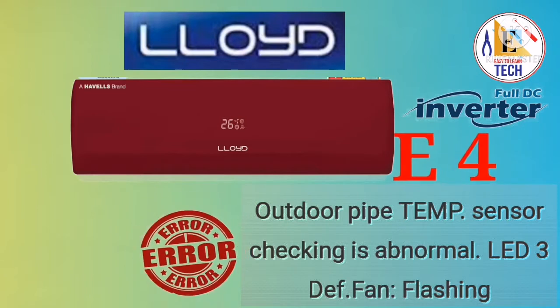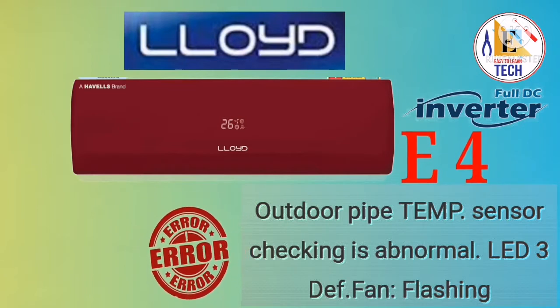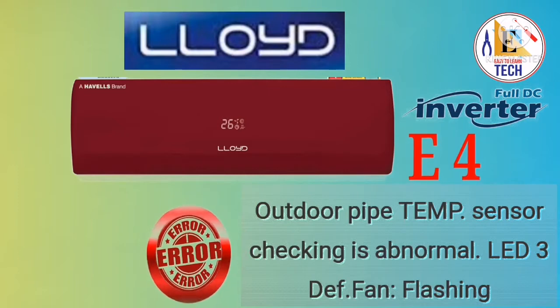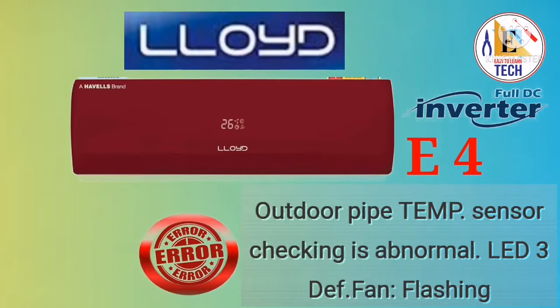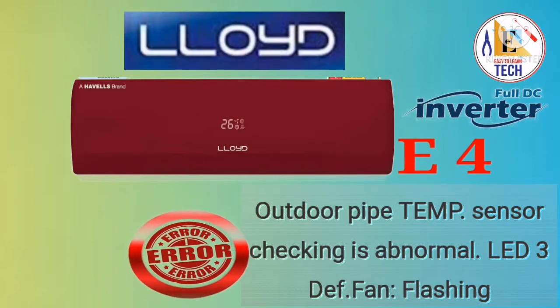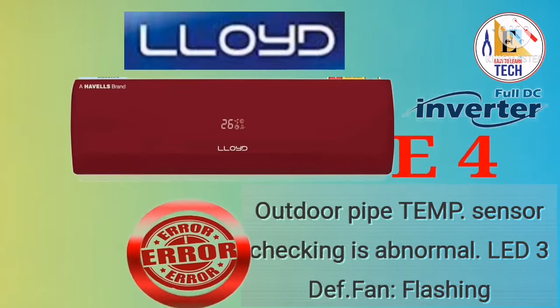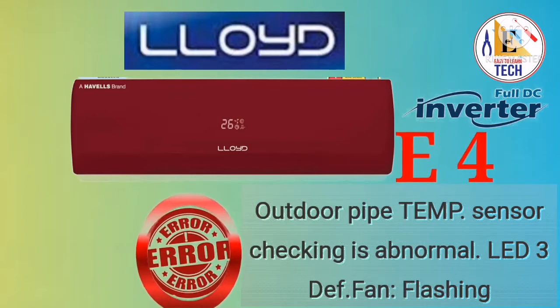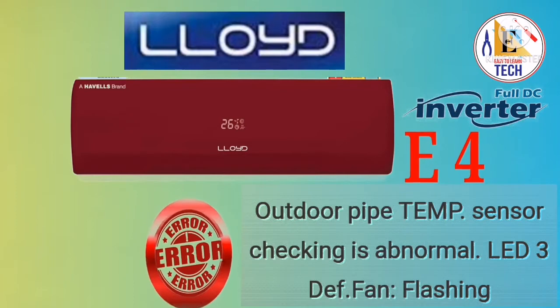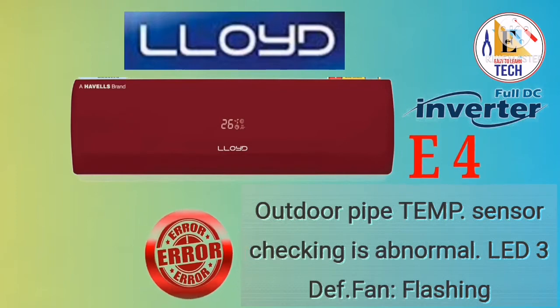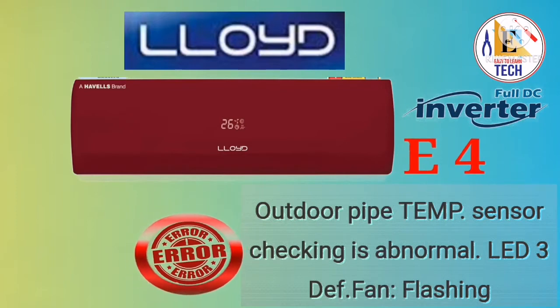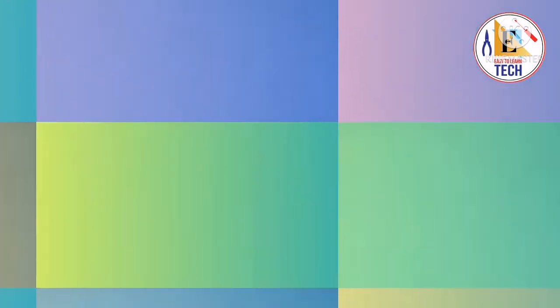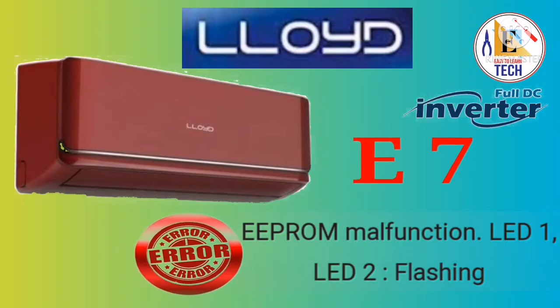If the resistance is good, then you have to check whether the power supply coming from the outdoor PCB to the sensor is good or not. Sometimes if it is short, at that time you will not see any resistance in your outdoor pipe temperature sensor. If you see that the outdoor pipe temperature sensor is good, then you have to change the PCB and you will get the solution for the error E4. Let's see the next error code.